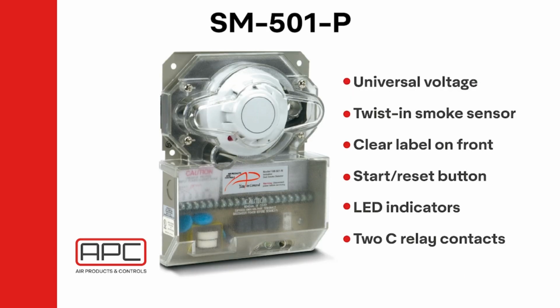The SM501 is a 4-wire conventional duct smoke detector. This detector is also offered with photoelectric heads, and has universal voltage that includes the higher range of 230 volts AC. The SM501 features a test and reset button to reset the unit with the cover on.